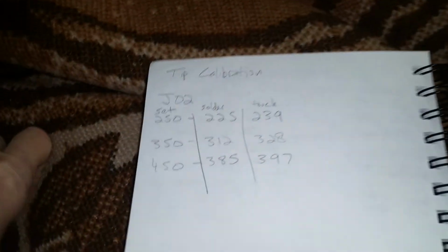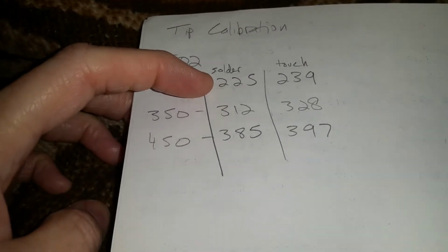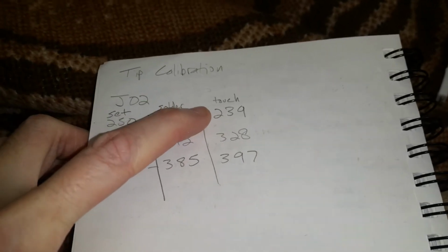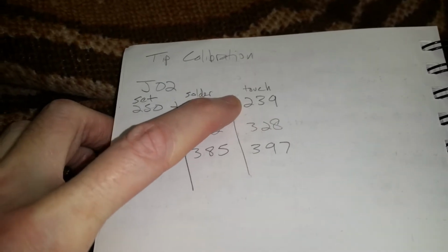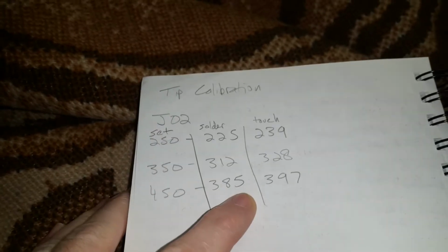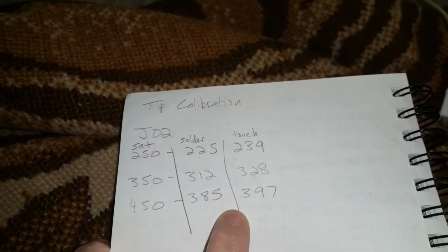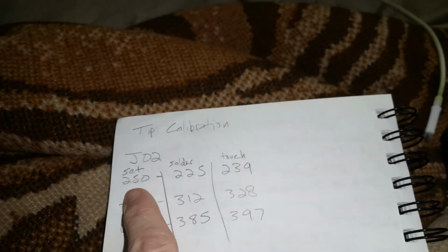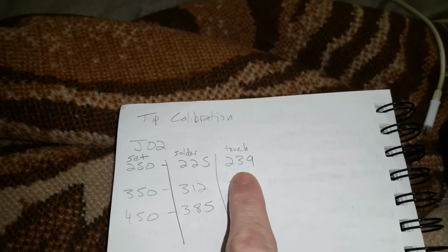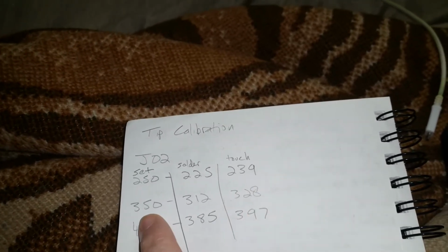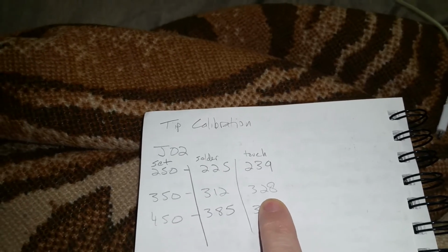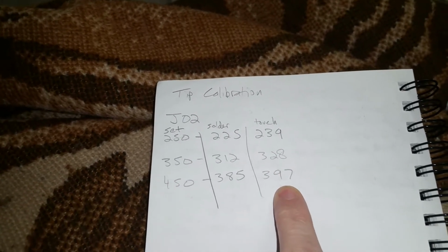Anyway, here is what I've currently measured. I set the iron to 250. If I touch only solder to the temperature probe, I get 225, and then if I touch the actual tip really well, kind of move it around to get the highest reading, I get 239. And all of these readings pretty much are the same as what I measured earlier, so I've got good repeatability. And basically this first one at 250, it's about 11 degrees down. At 350, 22 degrees down. At 450, about 53 degrees down.